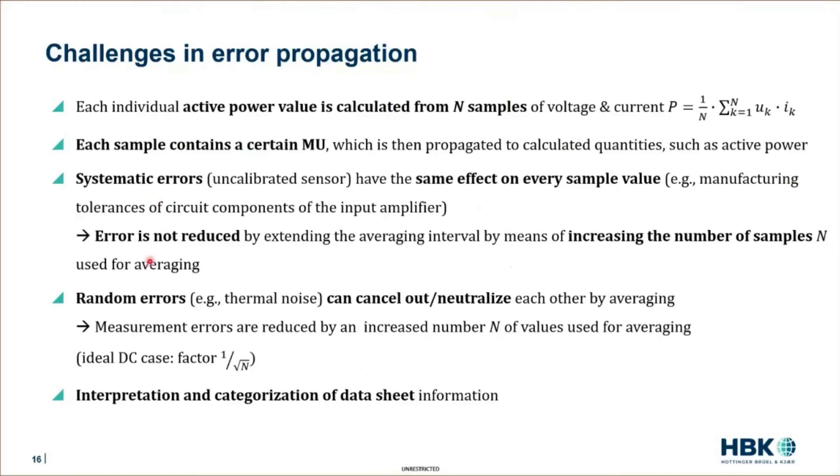On the other side, we have random errors such as noise, for example. And if you think about noise, this is not the same from sample to sample. For one instant in time, it can be a bit too big. For the next instant in time, it is a bit too small. And therefore, it may cancel out each other from sample to sample. And for this, these errors may be reduced by increasing the averaging interval. That's also the reason why a lot of people who need high accuracy, they do not average the active power over only one fundamental cycle. They take a multiple integer of it.